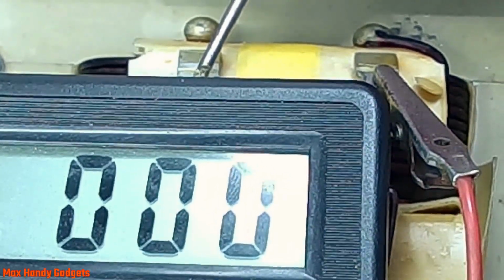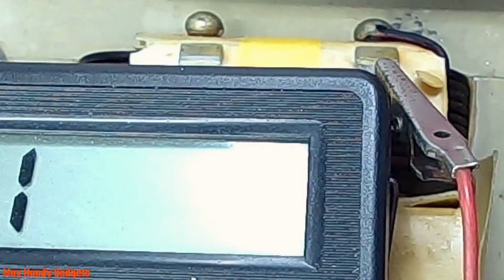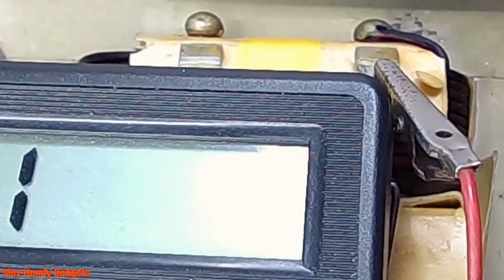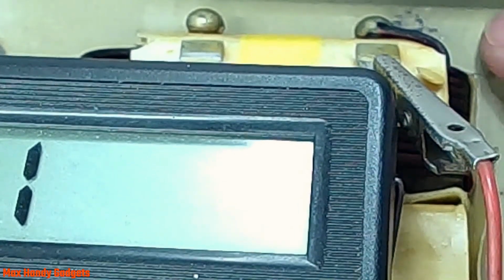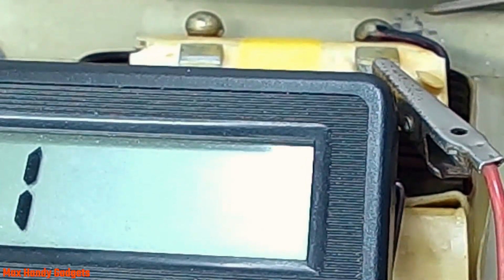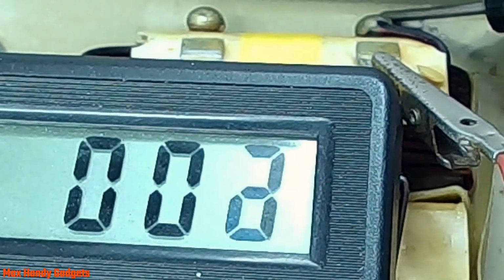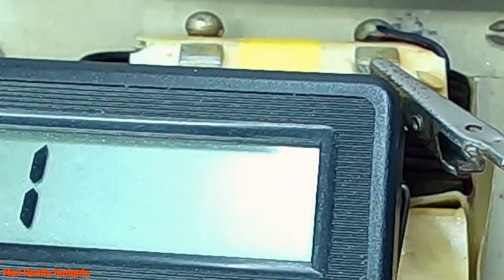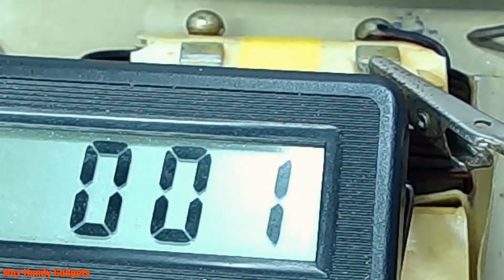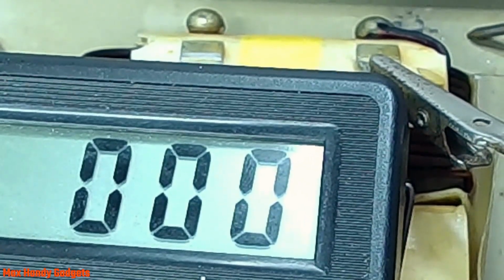So that's bad. Now let's test the body of our transformer, to see if there's a short between this post and the ground, the body of the transformer. We shouldn't have anything touching, but let's see. Ready? See that? Look, it's a dead short to ground.